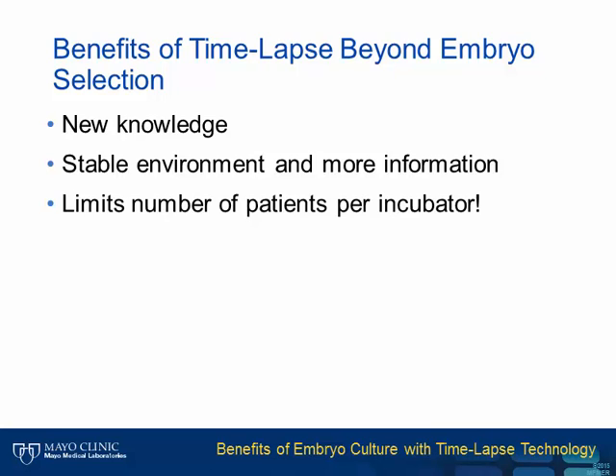For time-lapse systems, typically four to six patients are cultured per incubator, and door openings are limited. Whereas big-box incubators have unlimited numbers of patients with a high number of door openings, resulting in longer recovery periods and thus negatively influencing the quality of the culture environment.